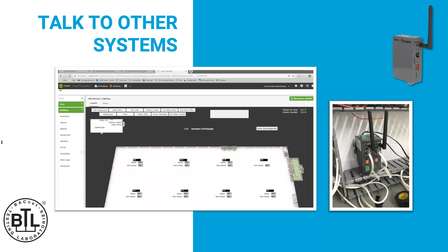Problem 4: I need lighting that will integrate with my facility's operations. If you have a corporation or large enterprise with a parking structure, it's not uncommon for them to already have some sort of building automation system for control of other lighting systems, HVACs, and other building management components. They require that the lighting controls can talk to those systems, so with our BMS gateway, we can be controlled by those existing building automation systems using BACnet or Modbus.